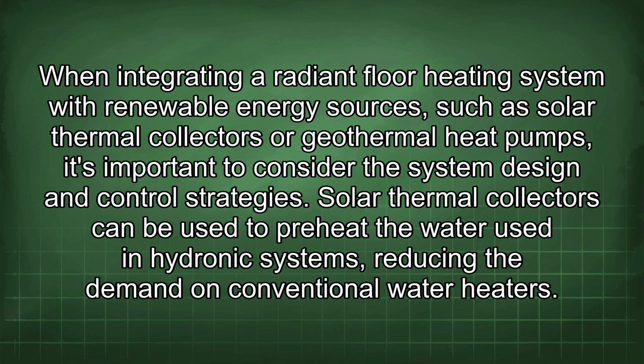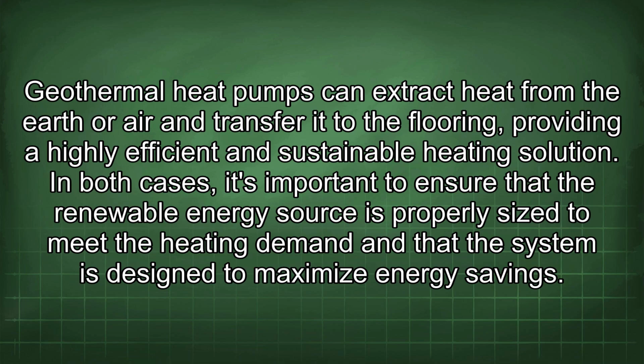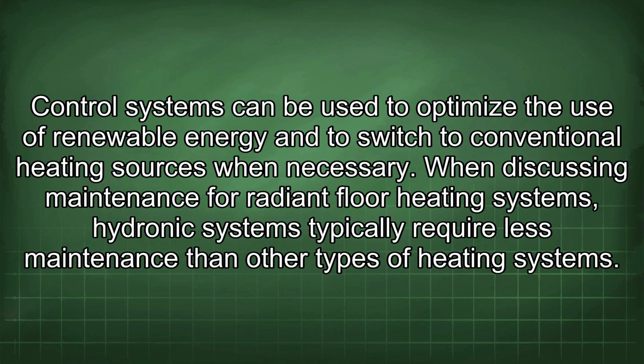When integrating a radiant floor heating system with renewable energy sources, such as solar thermal collectors or geothermal heat pumps, it's important to consider the system design and control strategies. Solar thermal collectors can be used to preheat the water used in hydronic systems, reducing the demand on conventional water heaters. Geothermal heat pumps can extract heat from the earth or air and transfer it to the flooring, providing a highly efficient and sustainable heating solution. In both cases, it's important to ensure that the renewable energy source is properly sized to meet the heating demand and that the system is designed to maximize energy savings.